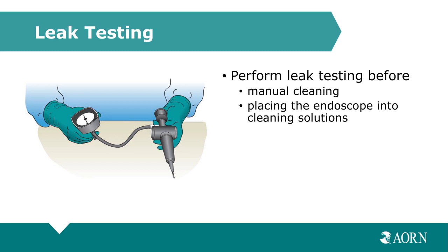Flexible endoscopes that are designed to be leak tested should be leak tested, and they should be leak tested after each use and after any event that may have damaged the endoscope. Leak testing should be performed before manual cleaning and before the endoscope is placed into any kind of cleaning solutions. Now, the evidence fully supports leak testing because this gives us a method to help ensure that the endoscope has not been compromised and that it is safe to use on the patient.